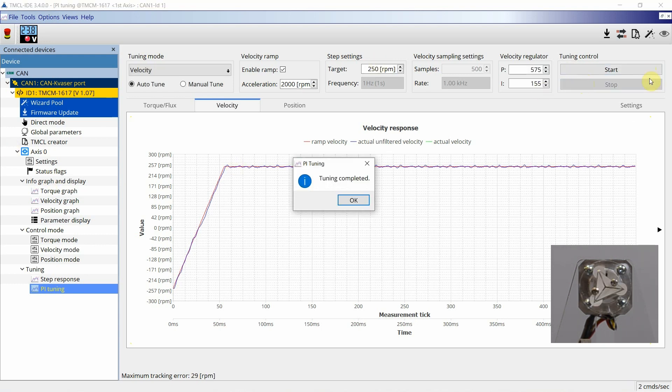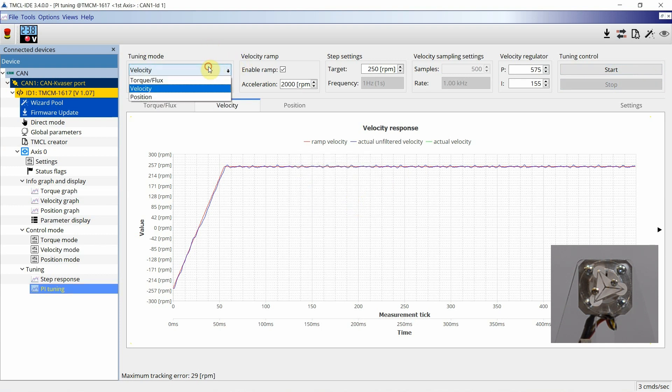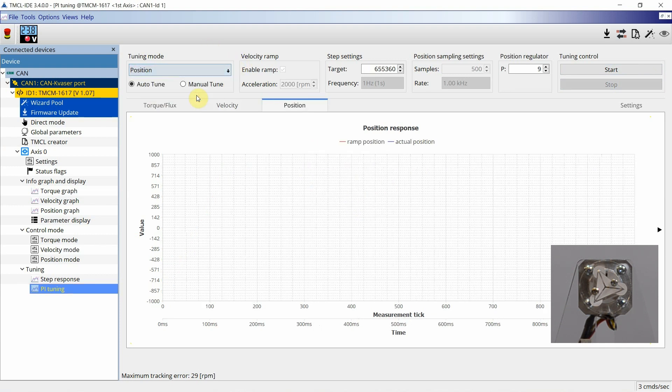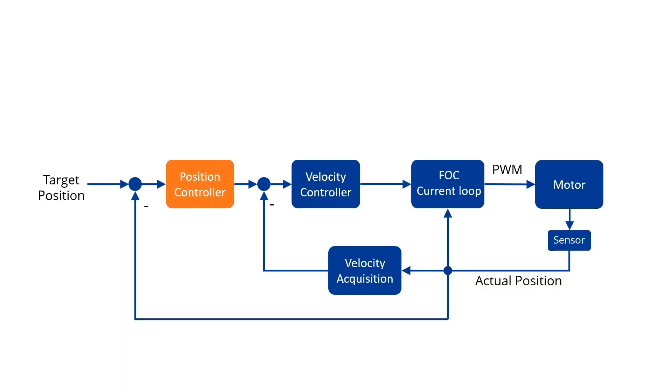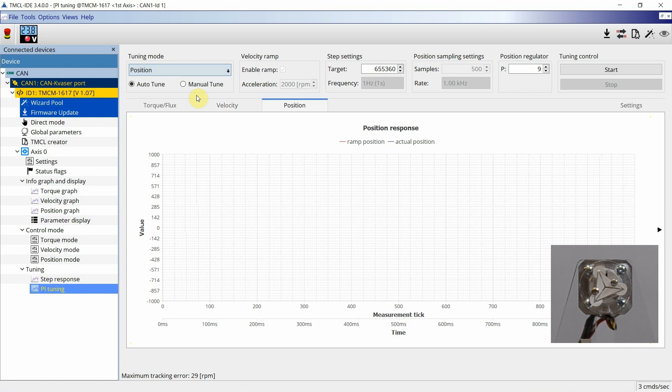As third and final step, the position controller is being tuned. The position loop is cascaded and is dependent from the velocity loop settings including the ramp settings. For this reason, the ramp setting is only configurable in the inner velocity loop.